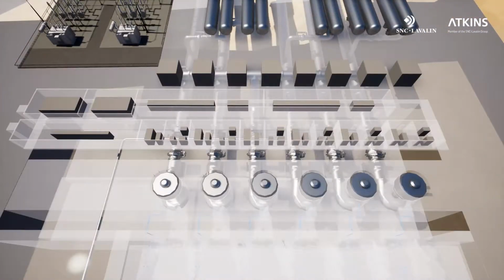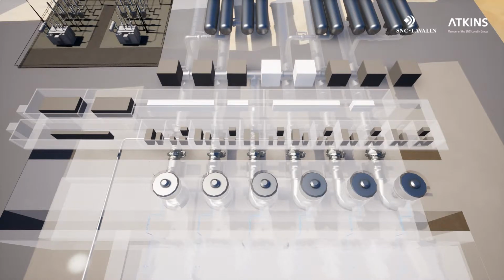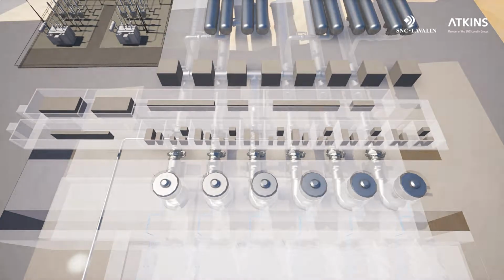Primary distribution is achieved by 2 separate, fully rated indoor switchgear assemblies. Each pump has a dedicated transformer, switchgear, and control gear. This arrangement facilitates maintenance and eliminates the risk of a failure event impacting on more than one pump. Pump starting is implemented using a pair of static frequency converter units.